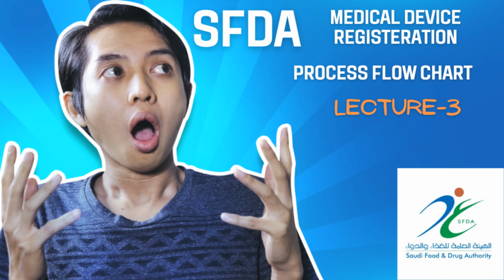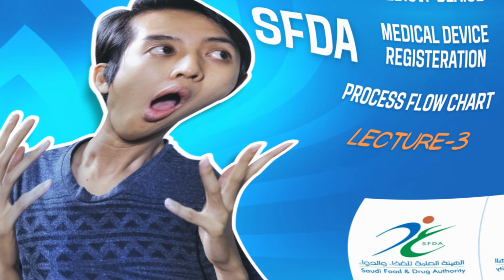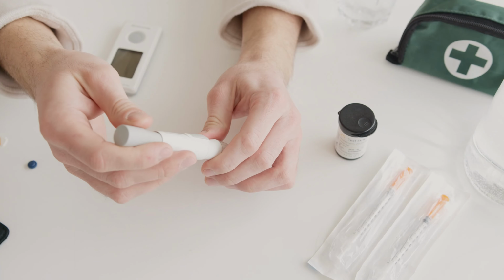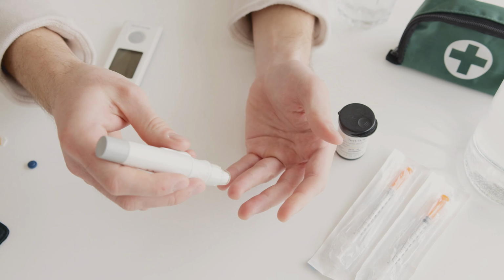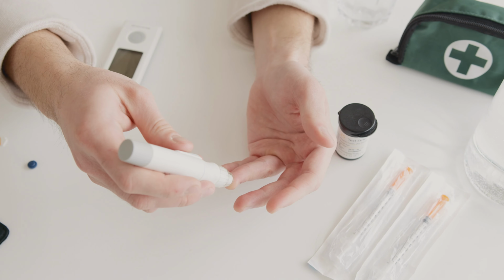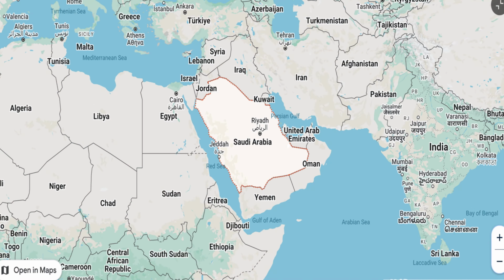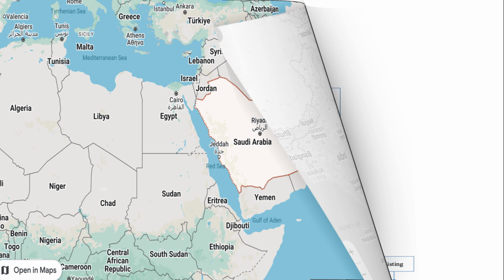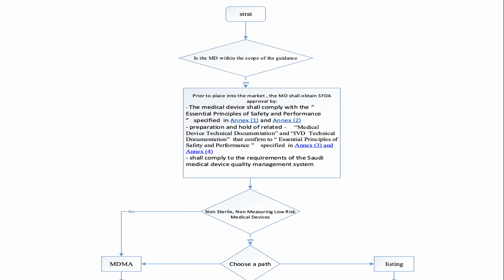So assuming that you have produced a new medical device for which a design is locked and all the required studies have been done, now you need to place your medical device into the territory of Saudi Arabia. Before you place it, you need to comply with the regulatory requirements. So the first step in the regulatory process arises by asking yourself whether this medical device falls within the scope of the guidance or not.